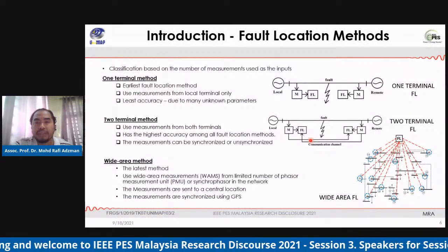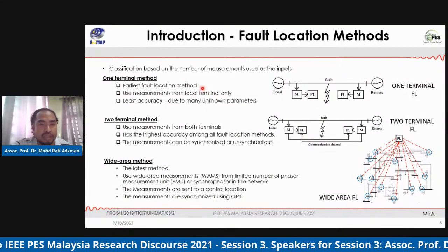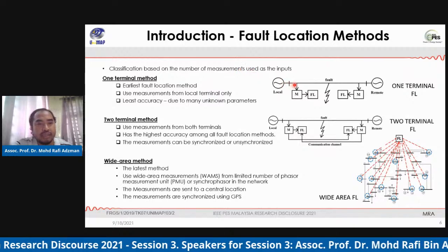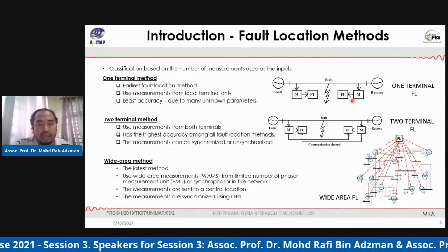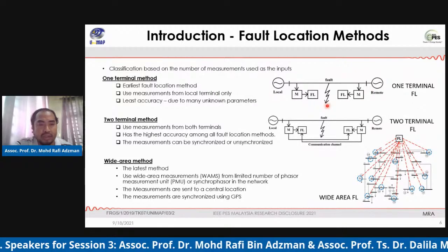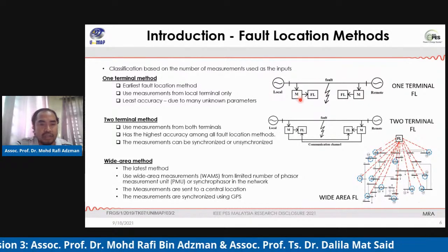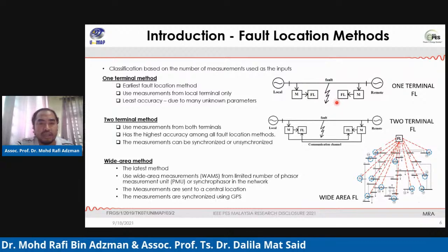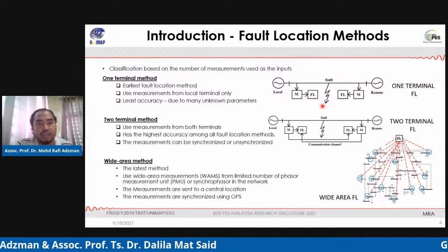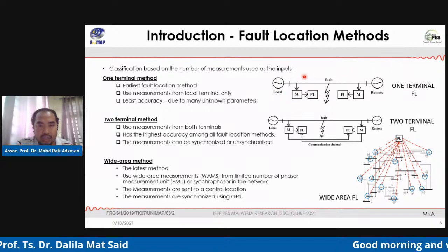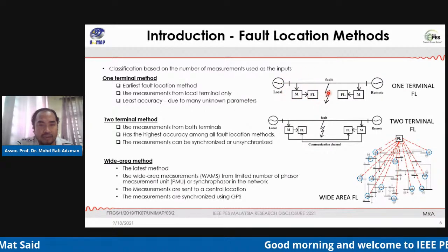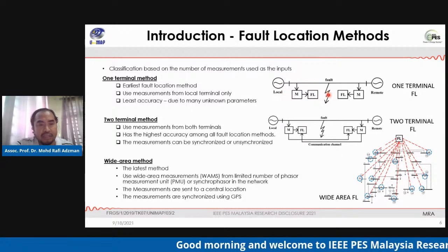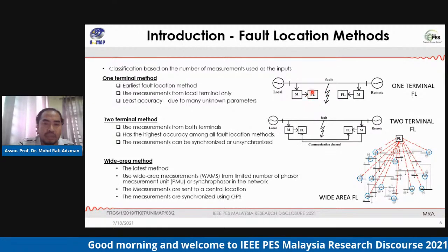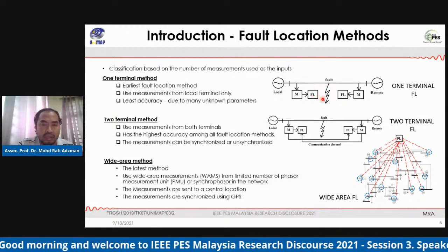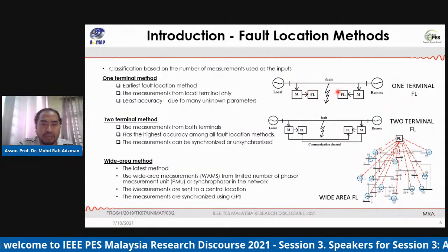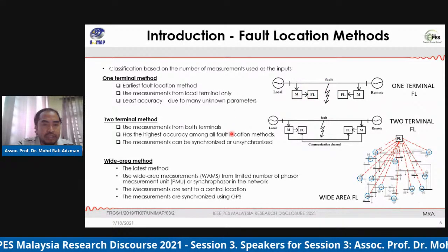So the fault location methods can basically be classified based on the number of measurements used as the inputs. And here we have a figure with an example of the one terminal method. It is the earliest fault location method, and it uses a measurement from the local terminal here. This kind of fault location method is less accurate compared to the others, because we need to estimate many unknown parameters.